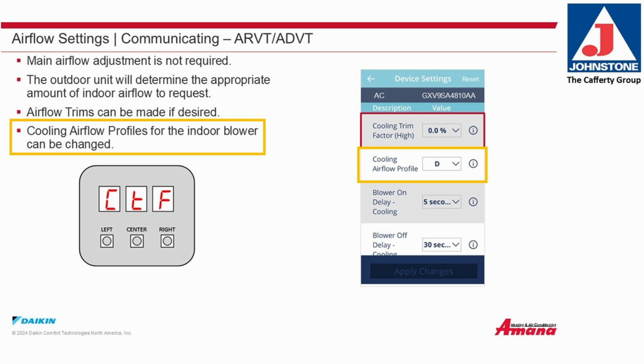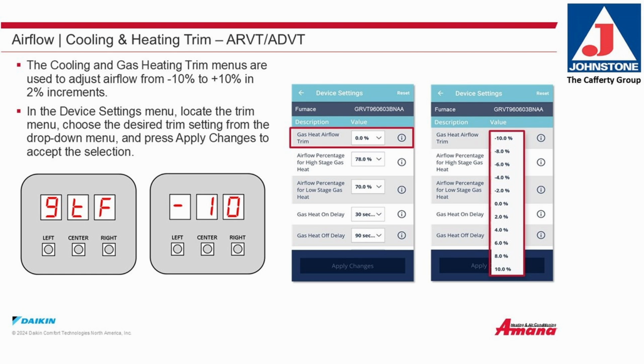Airflow, cooling and heating trim. The cooling and gas heating trim menus are used to adjust the airflow from -10% to +10% in 2% increments. In the Device Settings menu, locate the Trim menu. Choose the desired trim settings from the drop-down menu and press Apply Changes to accept the selection.